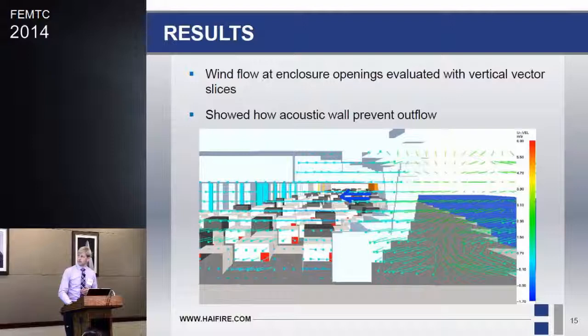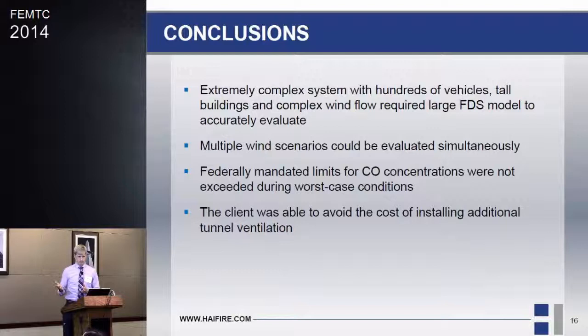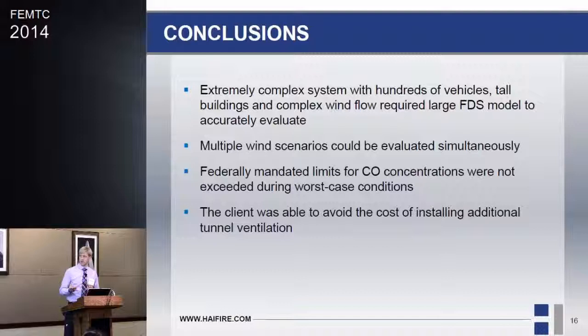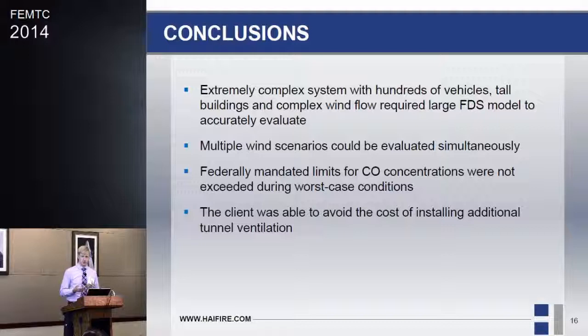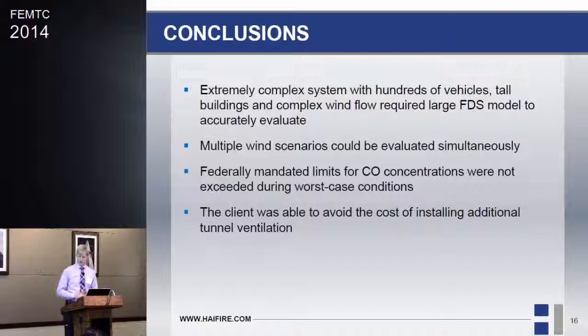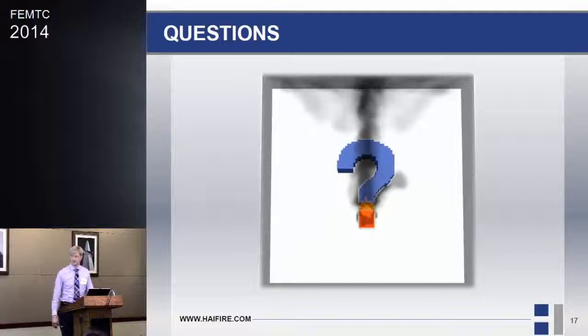In conclusion, this was an extremely complex system involving the interaction of vehicle exhaust, wind, and large buildings — especially the two tall buildings at each end of the roadway which disrupted the wind. We used a large FDS model and ran multiple wind scenarios simultaneously to identify the worst cases. The mandated CO concentration limits were not exceeded in any scenario, so the client could avoid the cost of installing additional mechanical ventilation.